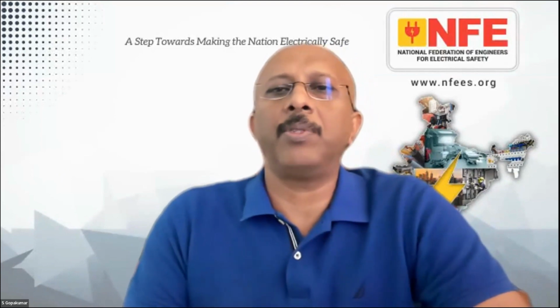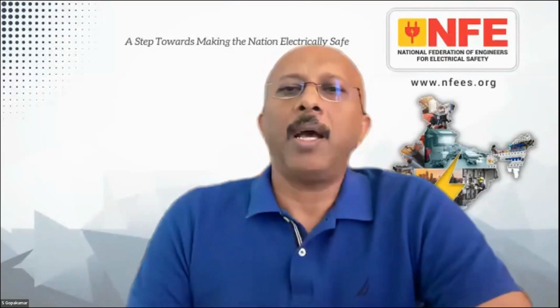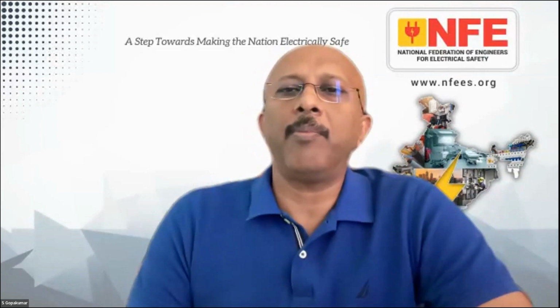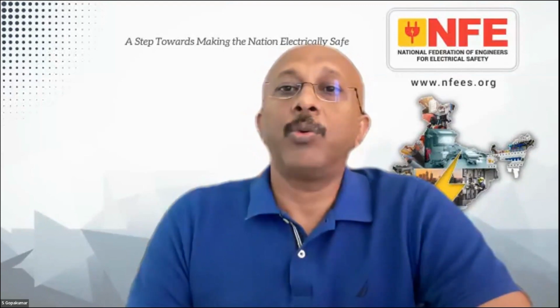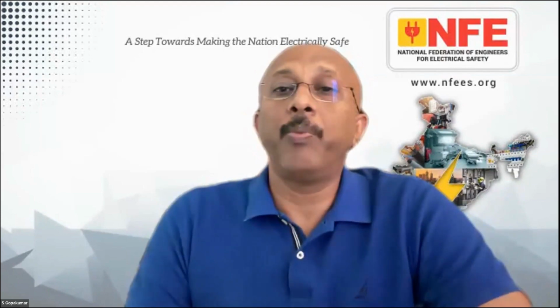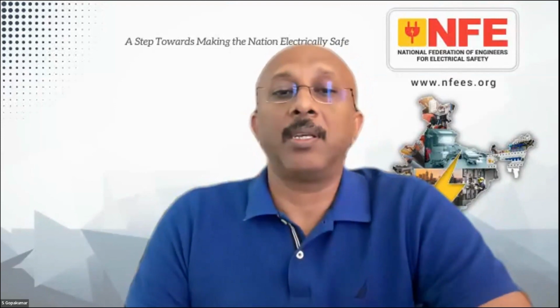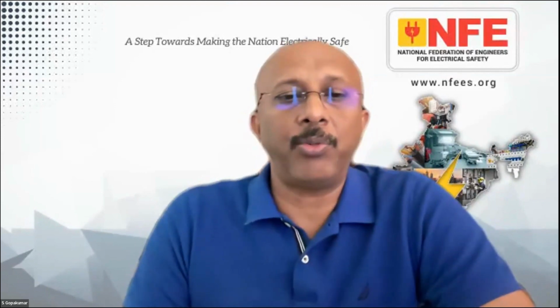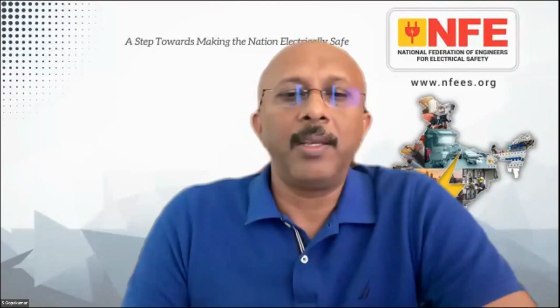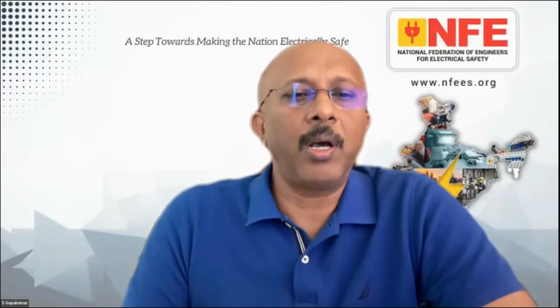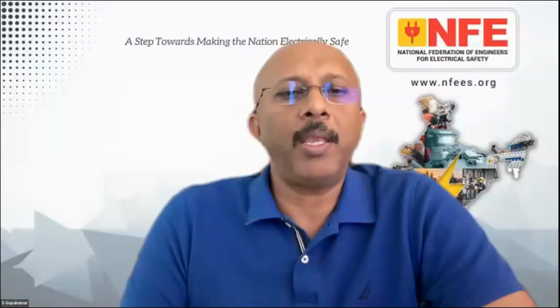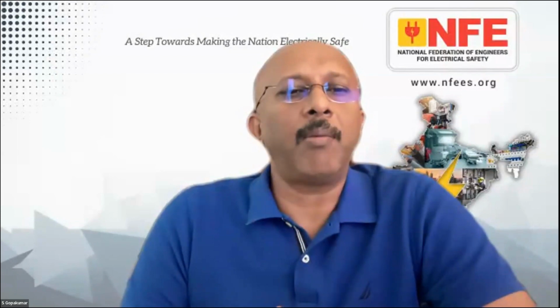Now we have a question from Mr. Desai. Can armor of XLPE cable be considered as ground wire conductor to carry prospective fault current in TNC system? What should be the earth loop impedance in this case? There are two parts of the question. In India, we always use armored cable. There is a steel armoring in the cable. The question is whether this armoring can be used as a fault return path.